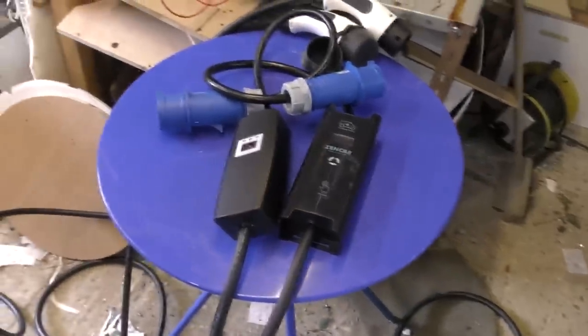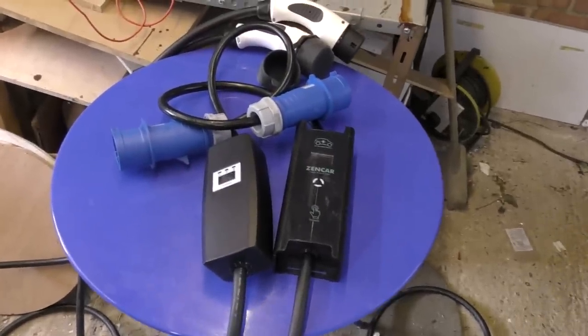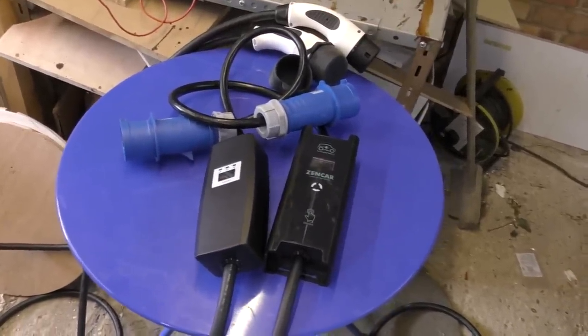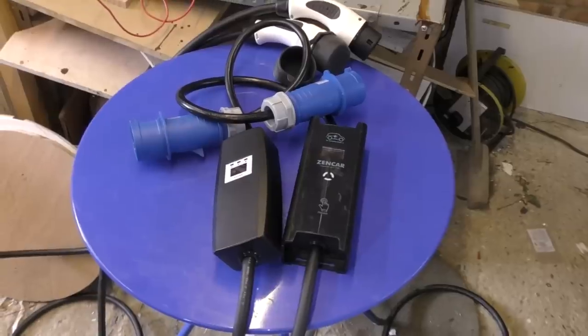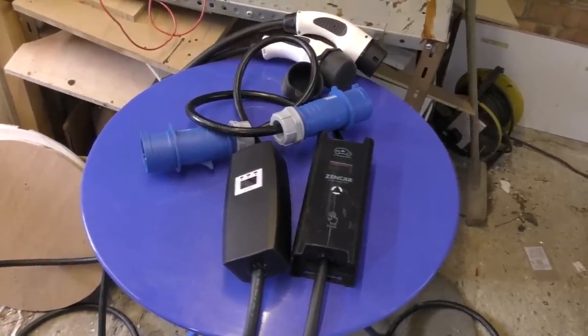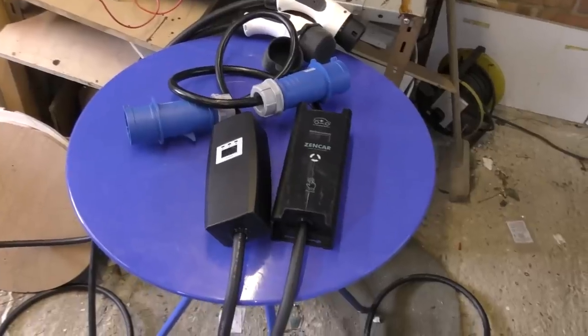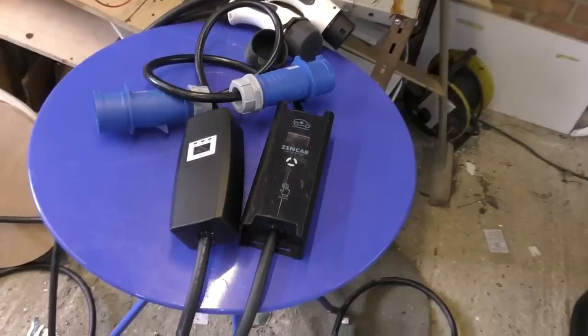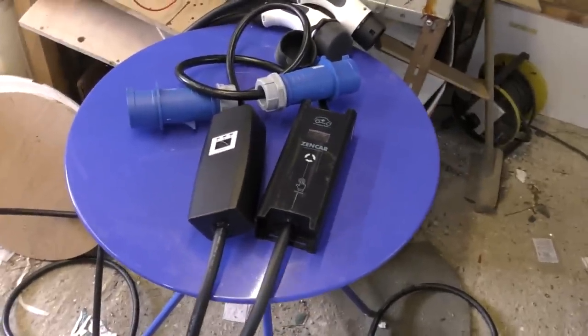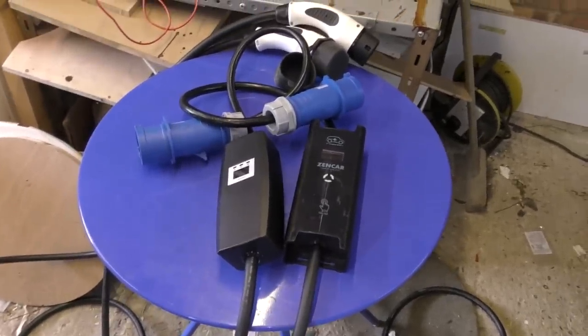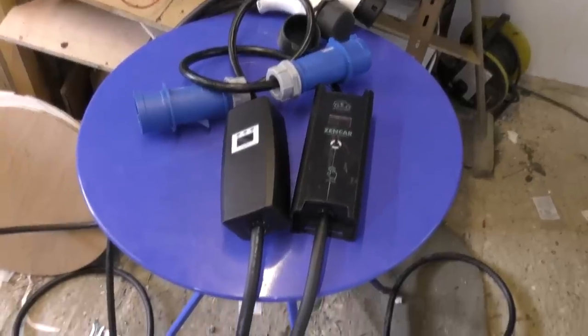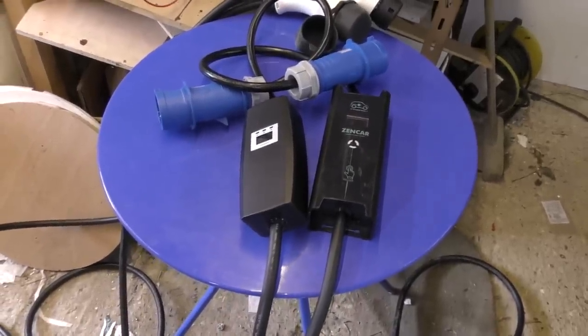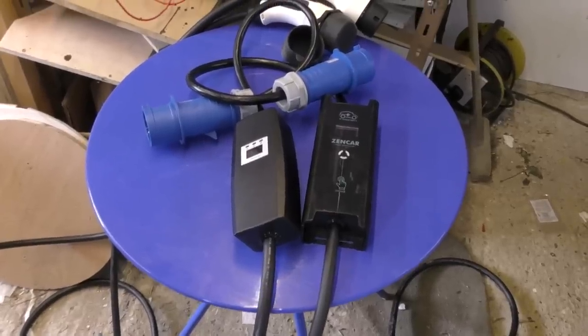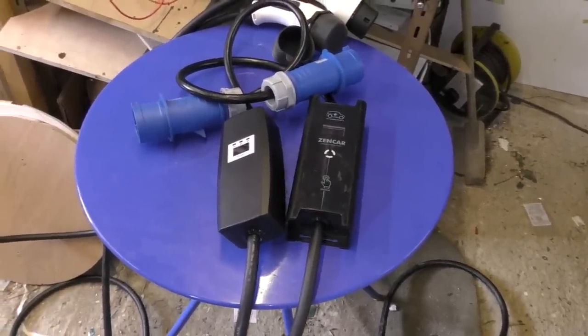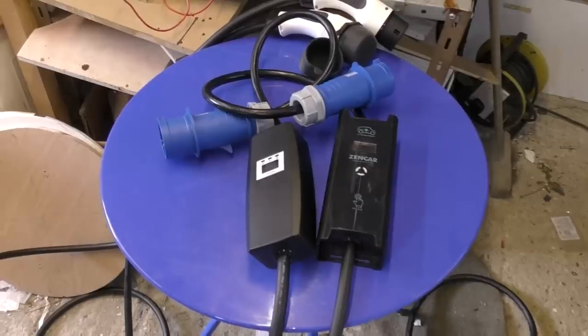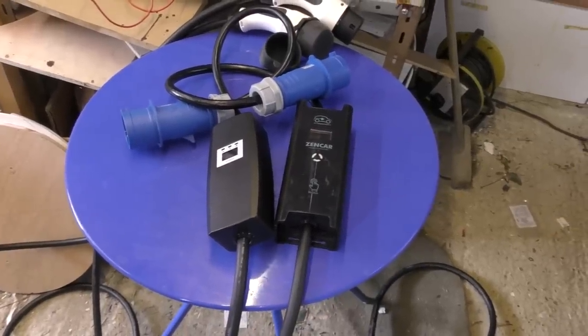Another sort of desirable feature, which has actually become part of the UK wiring regulations for hardwired fixed charge points, is that as well as the normal approximately 30 milliamps residual current trip, it also should trip on a DC leakage situation. Now, in a car you've got a massive 300 volt DC battery, so it's conceivable that some fault on the car could result in DC earth leakage. And there are actually 2 separate issues here. Firstly is actually detecting that situation. Now most standard residual current devices use an AC current transformer and won't detect DC leakage.